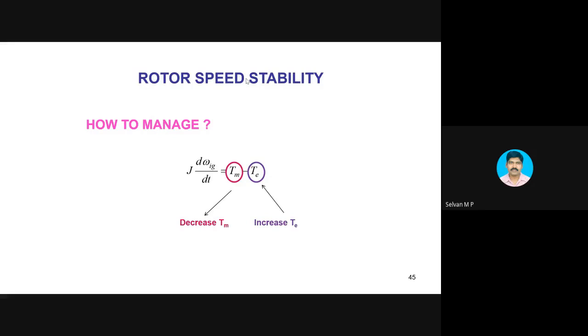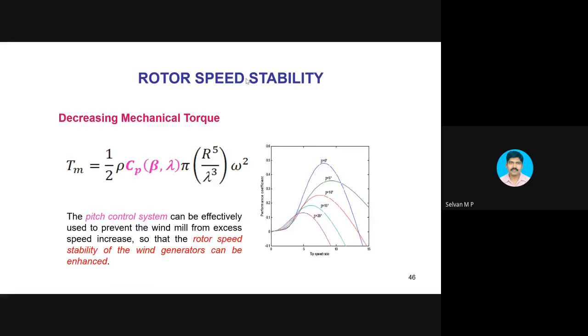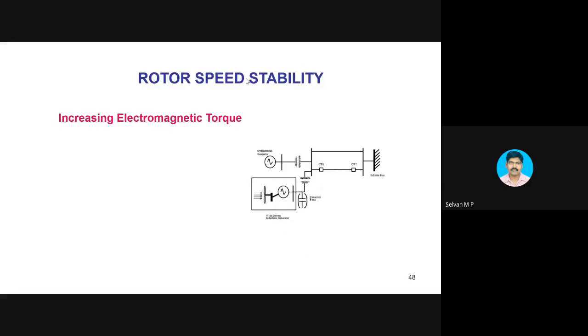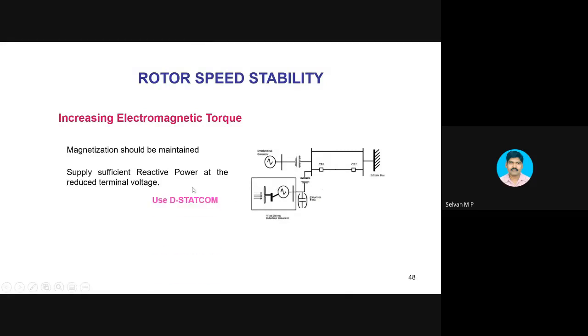So how to tackle the electromagnetic torque? We will forget about improving the mechanical torque. We will leave it. We can increase the electromagnetic torque. In order to increase the electromagnetic torque, I have to go with magnetization. So how to provide magnetization? I need to provide sufficient reactive power. Sufficient reactive power should be given with reduced terminal voltage. That is what is important here. Of course, every wind turbine will be provided with a capacitor bank. A capacitor bank can provide reactive power only at the rated voltage. If the voltage goes down, the reactive power output from the capacitor also comes down. Here I need more reactive power at reduced terminal voltage. That is possible with the help of STATCOM.